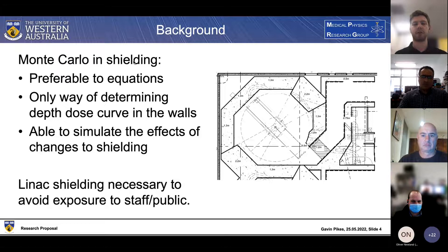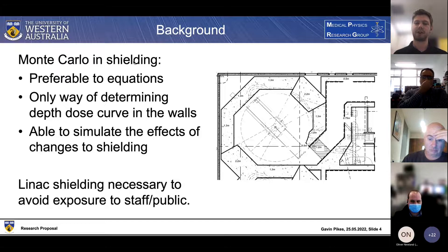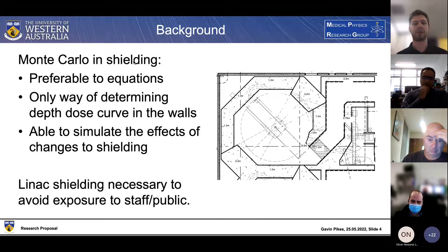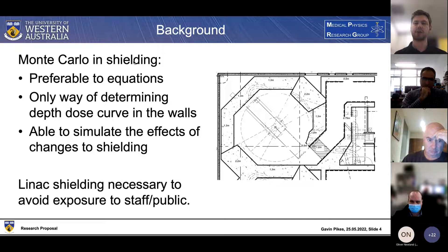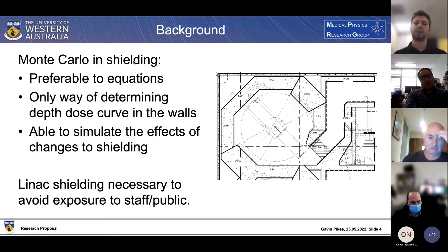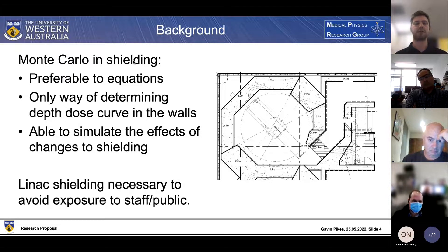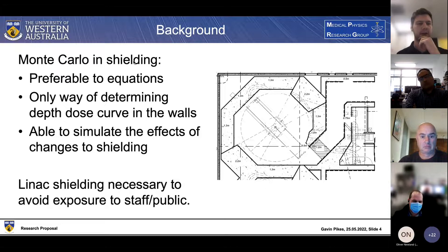Monte Carlo simulations are also the only way of determining depth dose curves within the walls themselves - we can't just insert an ionization chamber into the wall as that would affect the energy deposition quite drastically. Additionally, we're able to simulate different effects of changes to shielding through Monte Carlo. Say we wanted to change wall thickness - rather than making a mock wall and using a linac beam on it with an ionization chamber, we can instead just simulate it through Monte Carlo to quickly and easily see the effects.